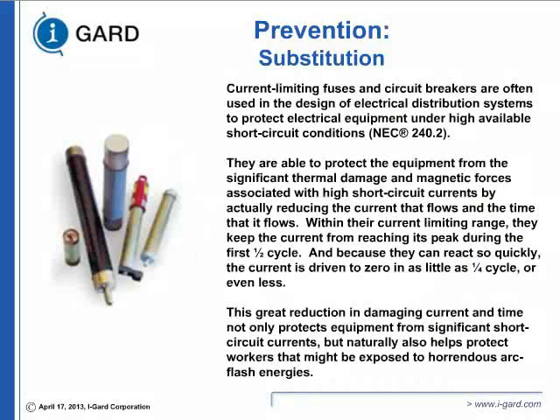First is current limiting fuses and circuit breakers. The National Electrical Code defines them for protection of equipment on a high available short circuit current condition. So it is going to limit the let-through. Now you cannot use a fuse to protect a breaker, for example, unless they have been tested together, because the downstream device has to be a passive device. They are able to protect the equipment because let-through current is less. If the let-through current is less, I squared t, the current squared and clearing time, is less. That then limits the damage to that equipment or the incident energy of the flash.